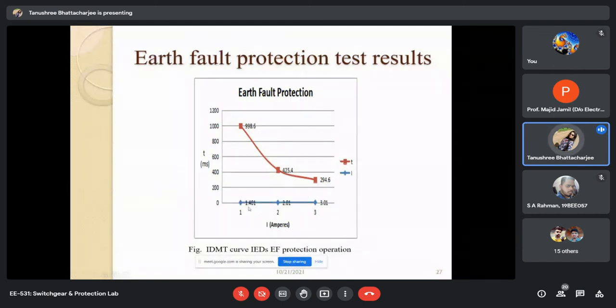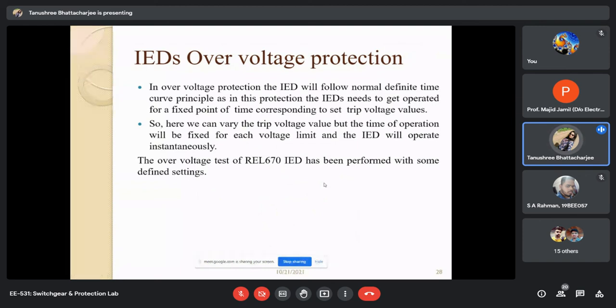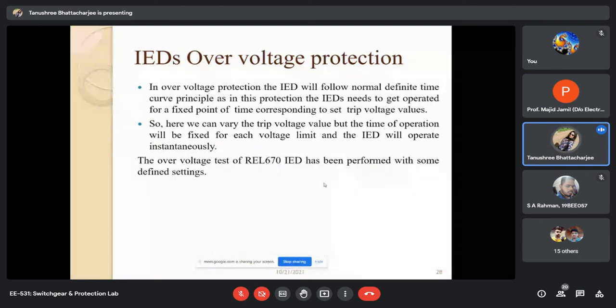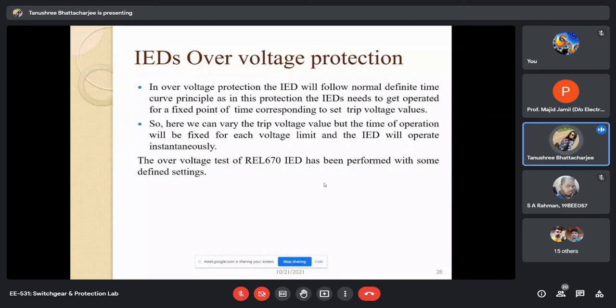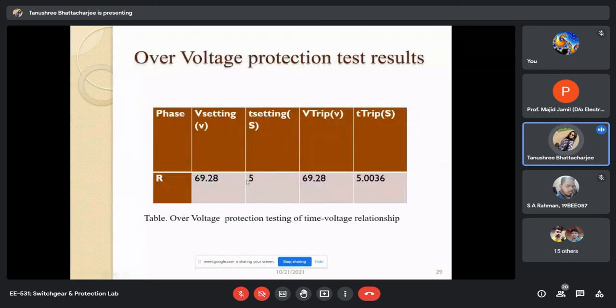Also in earth fault we have taken three increasing values of current, and these are the three values of time. In over voltage, as it will not follow any IDMT curve, it will be a fixed point of operation, because if we take any IDMT or any lagging of time, there can be a complete outage of a substation. That is why the operation of the IED in over voltage protection should be at a fixed point of time. So we set it within 5 seconds. If the voltage value is above 120%, then it should operate, and we are getting 5.0036 seconds.